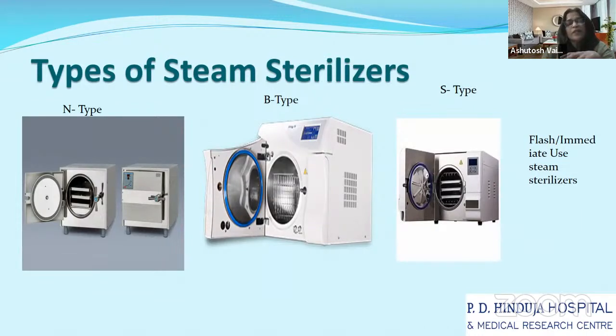And the B type is one wherein you have a fractionated vacuum, where your vacuum pump is so effective that it eliminates all the air within the chamber, which is the main hindrance in the sterilization process. Because if you have air pockets, your steam is not going to penetrate into them. And the last one, I call it flash, which is the terminology used for the immediate use steam sterilizer.